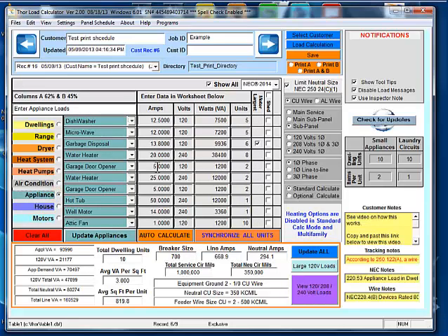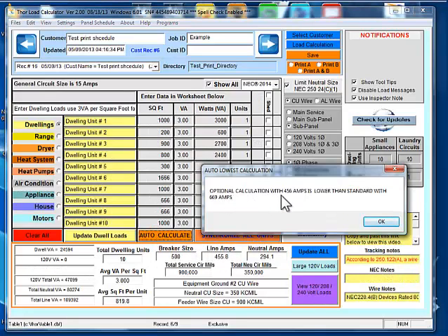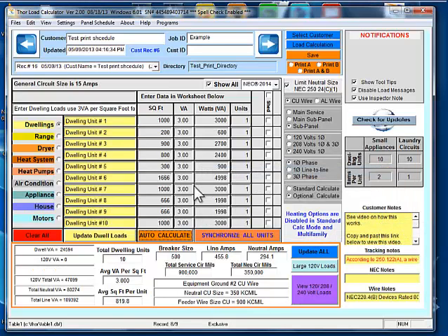And going to appliances, we have a variety of different items here. We have so many dishwashers, microwaves, water heaters of 2 different sizes, a hot tub for the very big units, well motor for the whole complex, and then we have 10 attic fans, 1 for each unit. Okay, so down here we can see that it requires a 700 amp to supply these 10 units, and the line amps calculate at 668.9. If we do auto calculate, we find that an optional calculation can reduce it to 456 amps. So we can go ahead and go with the optional calculation then.